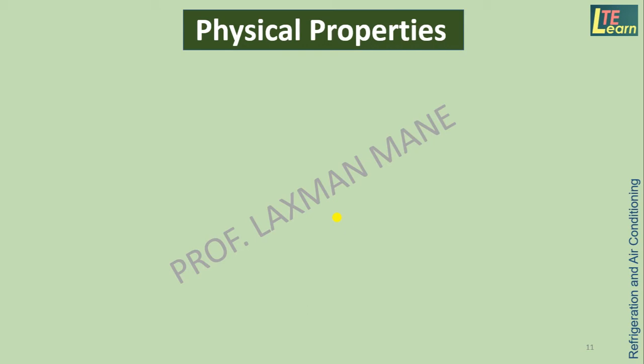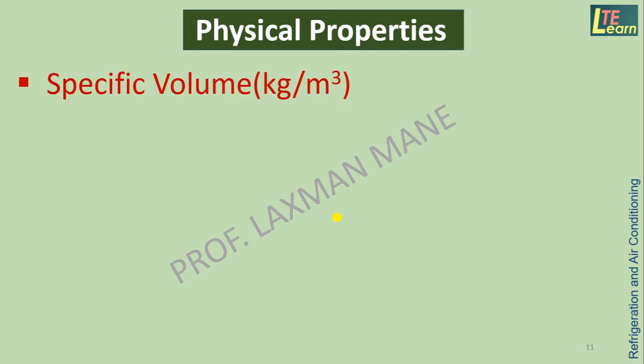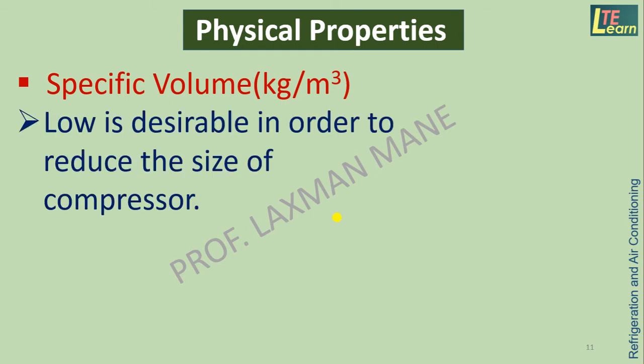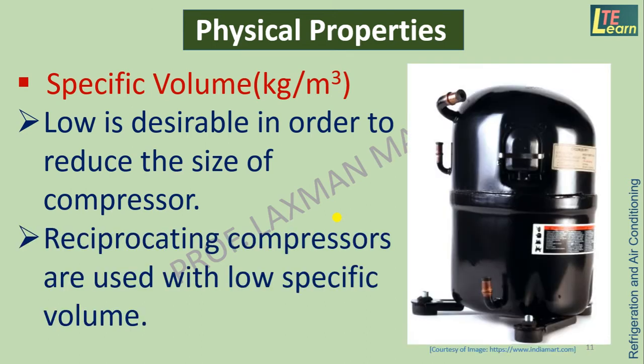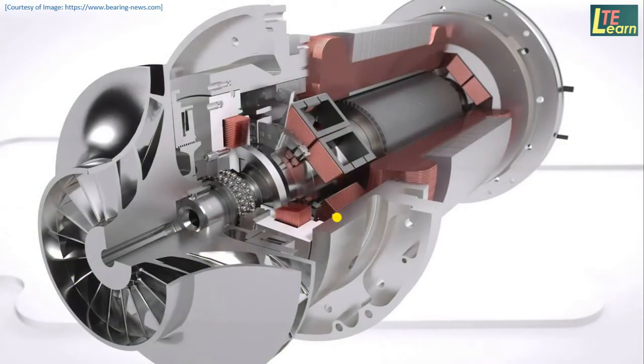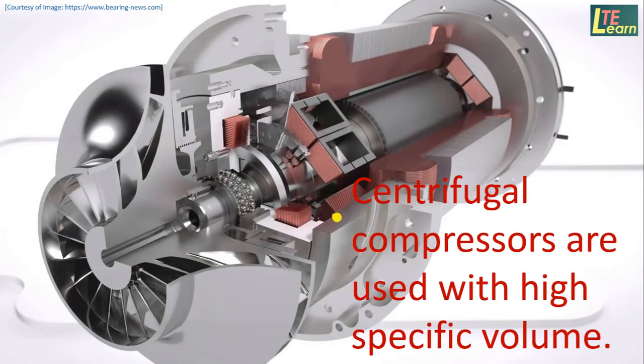Physical properties of refrigerants include Specific Volume — the volume in cubic meters of 1 kg of refrigerant — which should be low in order to reduce the size of the compressor. Hence, reciprocating compressors are used with low specific volume refrigerants. In the case of high specific volume, centrifugal compressors are used.